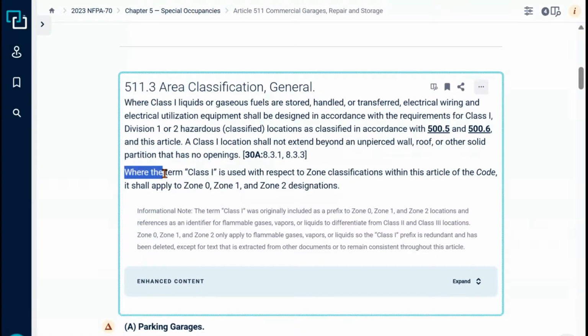Where the term class 1 is used with respect to zone classification within this article of the code, it shall apply to zone 0, zone 1, and zone 2 designations. So anywhere in here that it mentions class 1, even if it's talking about a zone 1, the restrictions in class 1 are also applicable to zone 0, zone 1, and zone 2. We'll look at all those zones too.